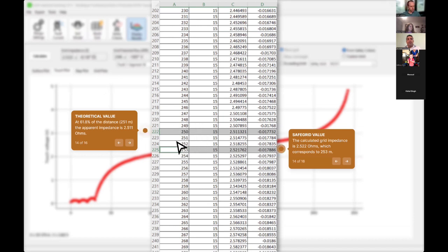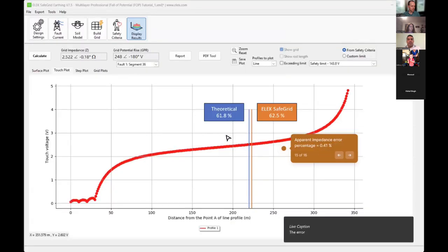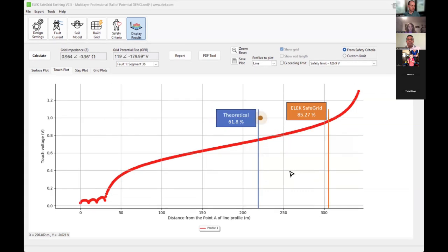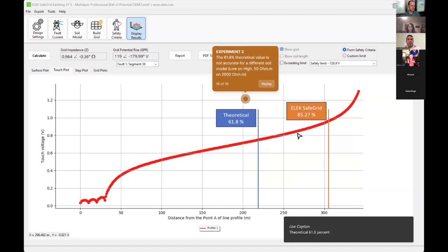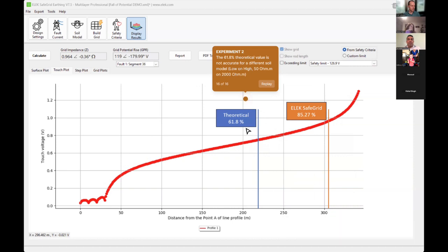So this is how we do an FOP test in SafeGrid and see whether the 61.8% limit is valid for our calculations. This is the final result: theoretical 61.8, but we get approximately 62.5, very close to 61.8. If you see a soil which is low over a high soil, we would see that the difference is much larger. Theoretical 61.8, but we would get only 85.27. Some of the limitations Jason will touch on a bit later. Thank you.